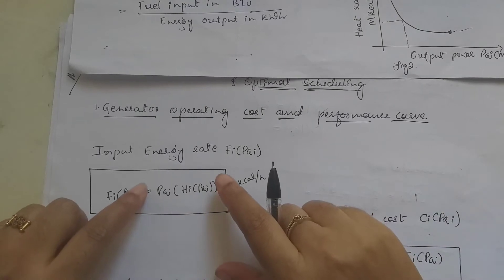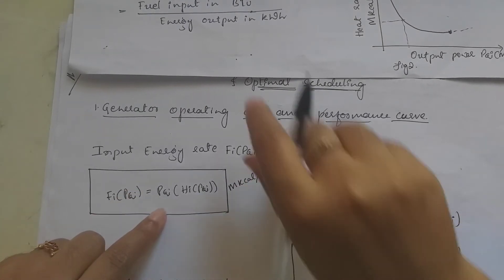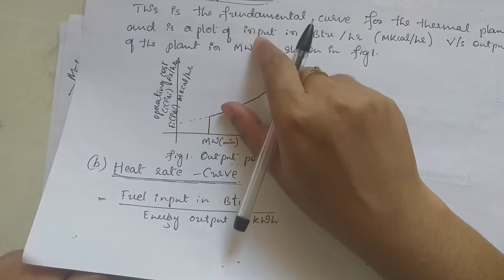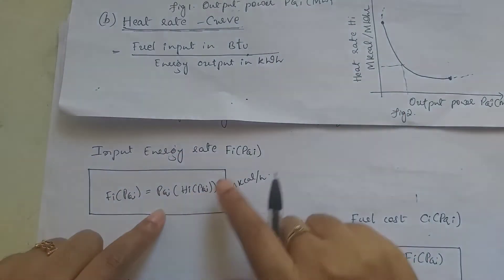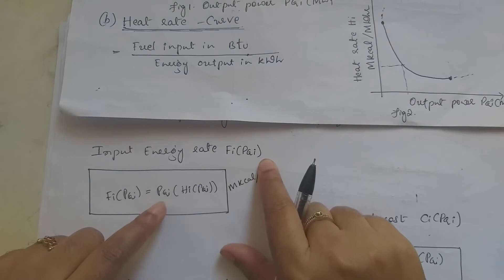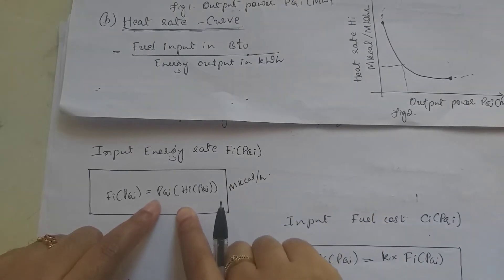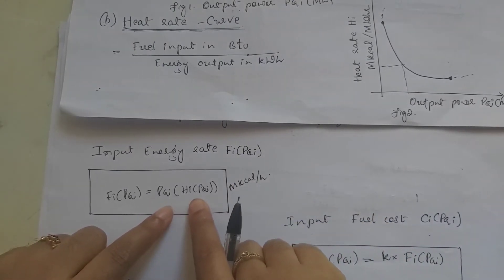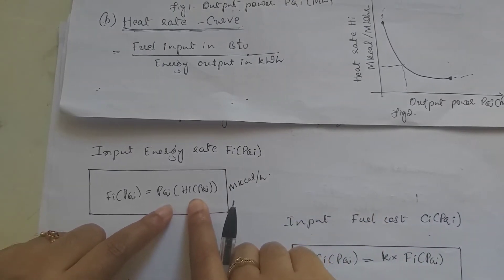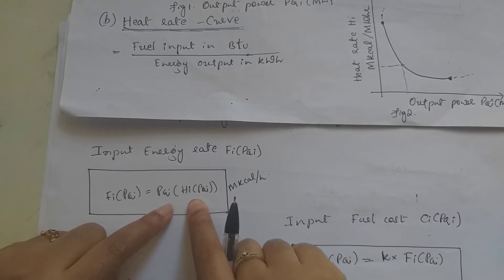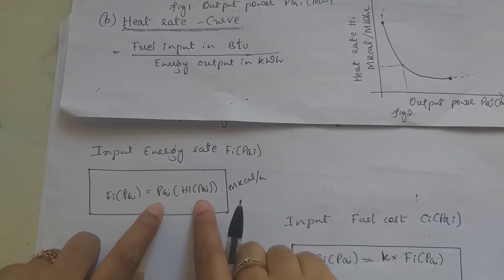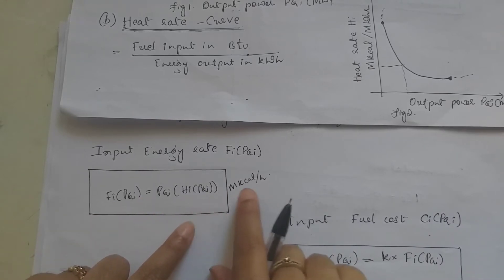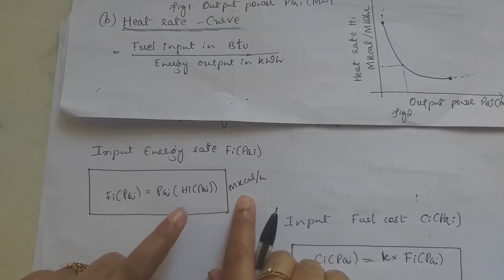The input energy rate is given by the input-output curve and is represented by Fi(PGi), given by the formula PGi multiplied by Hi(PGi). Hi is obtained from the heat rate curve. The heat rate curve is approximated as: Hi(PGi) = Ai' / PGi + Bi' + Ci' × PGi, with units of m kilocalorie per megawatt hour. Therefore Fi(PGi) = PGi × Hi(PGi), and the input fuel cost is K × Fi(PGi), where K is a constant. The unit of Fi is m kilocalorie per hour.